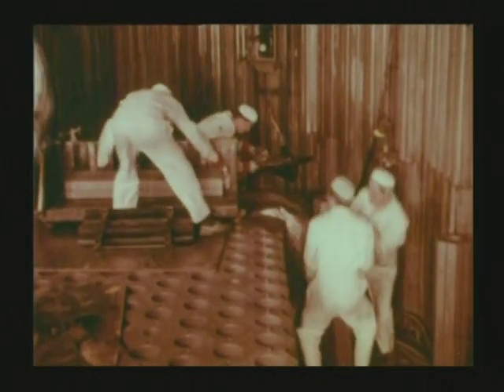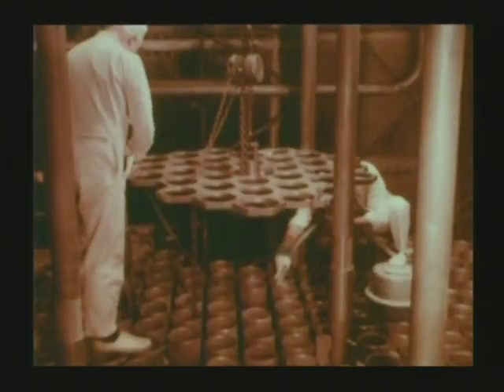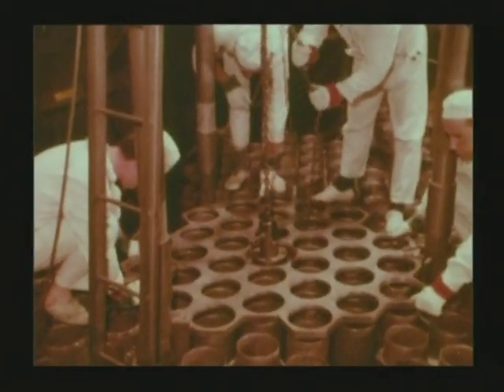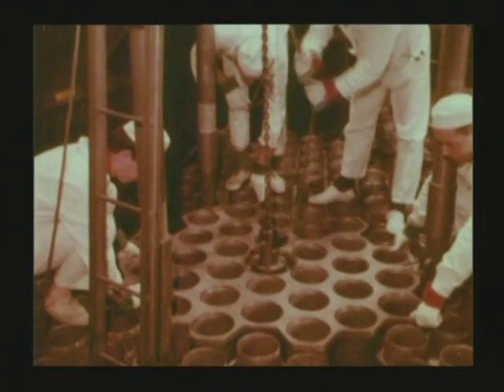Once in position, the reactor crown is next to receive its heat insulation and then its protective cladding. As this operation is completed, the construction of the reactor core can begin. Steel posts set upright next to each other and trussed at the top by a chain form a sort of girdle inside which the stacks of graphite are to be confined. The graphite is stacked in courses of hexagonal blocks in which channels are provided to receive the fuel elements. The channels, numbering 3,300, emerge beneath the reactor crown. To guard against distortions, honeycomb plates are used to brace the channels in independent cells of 33 channels each.